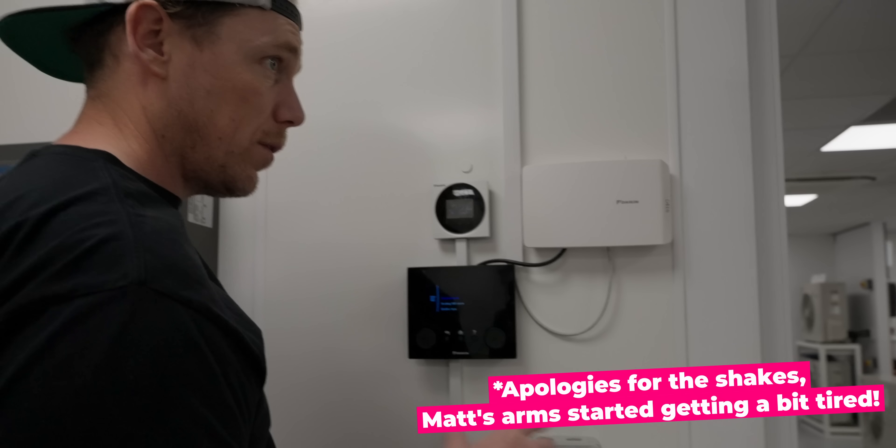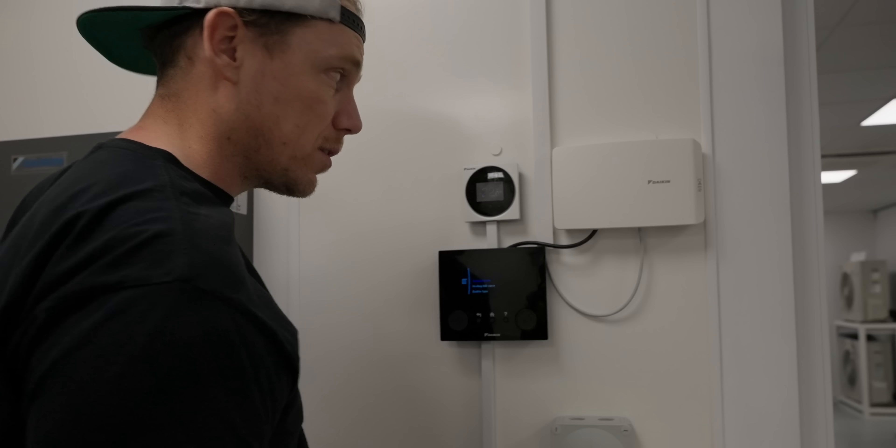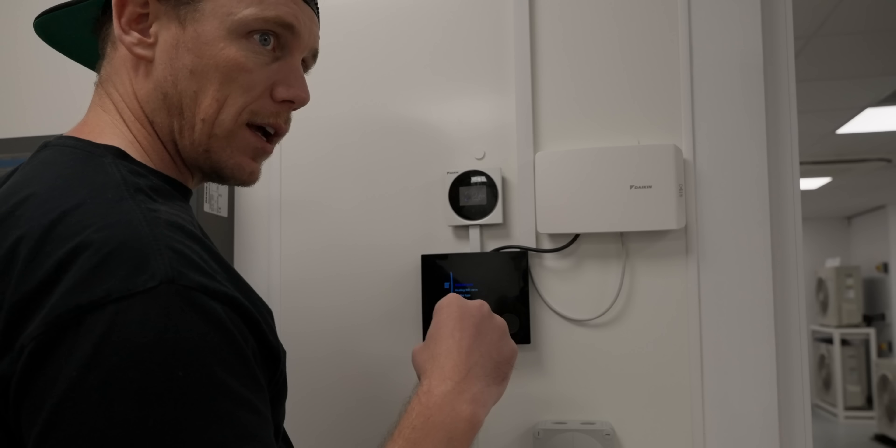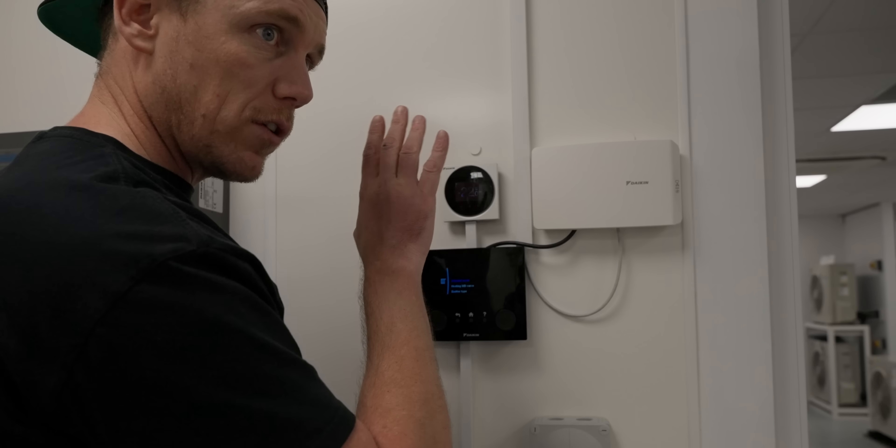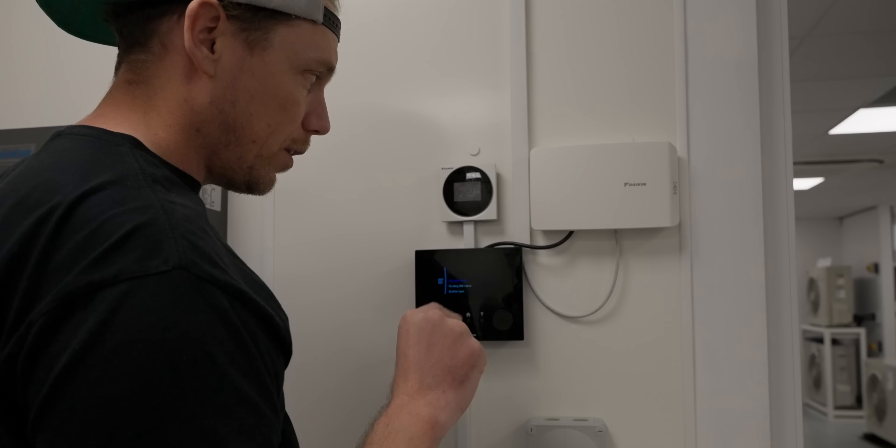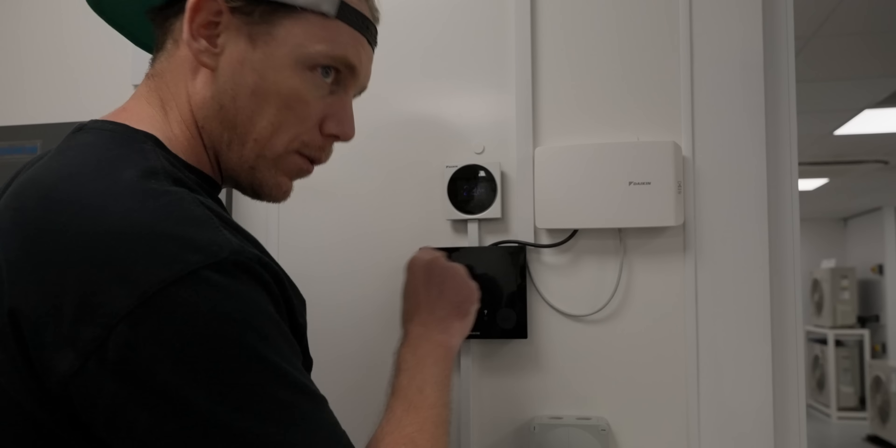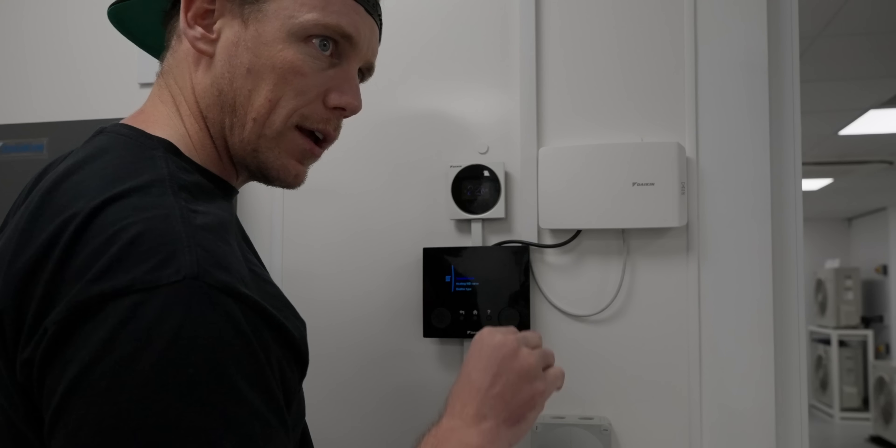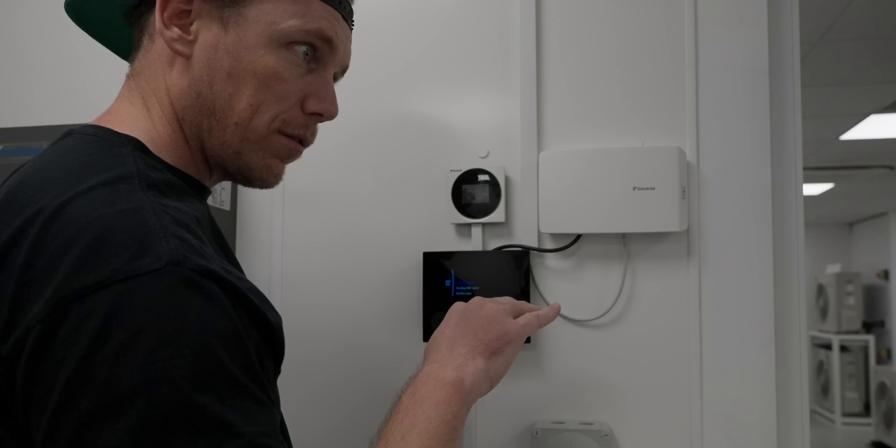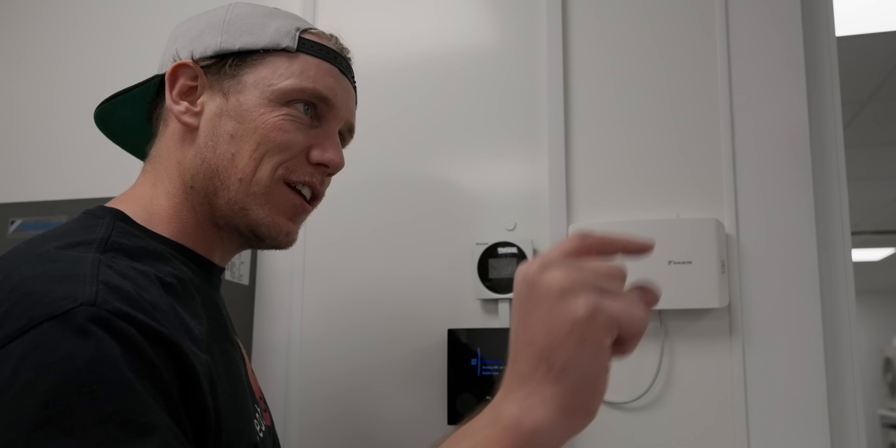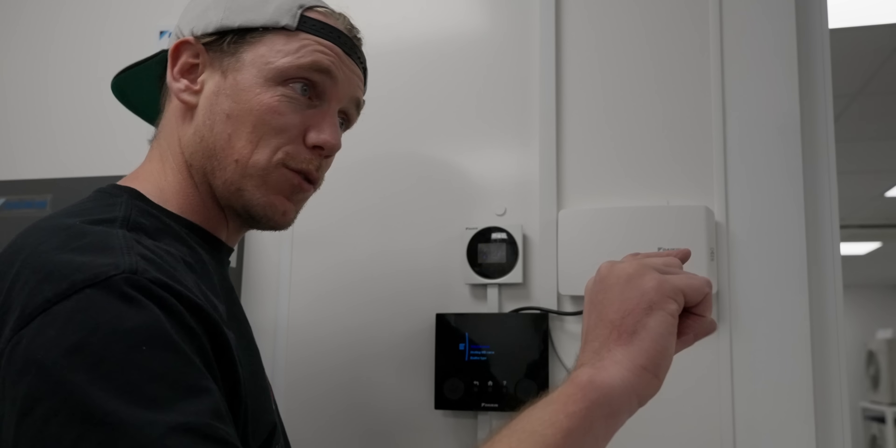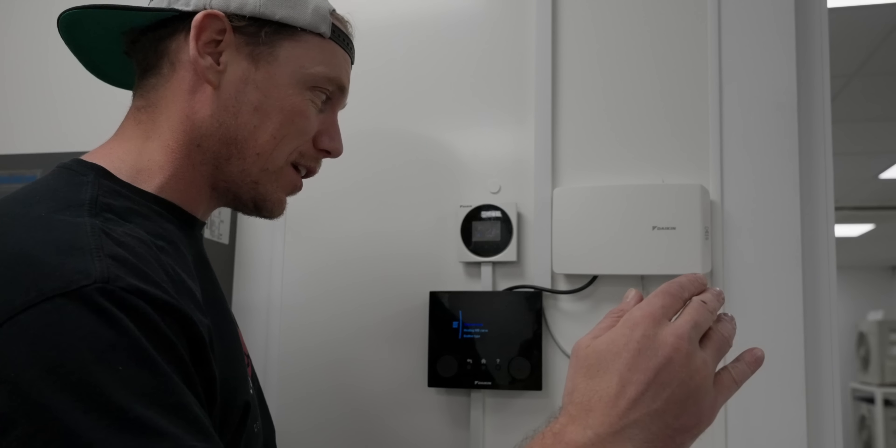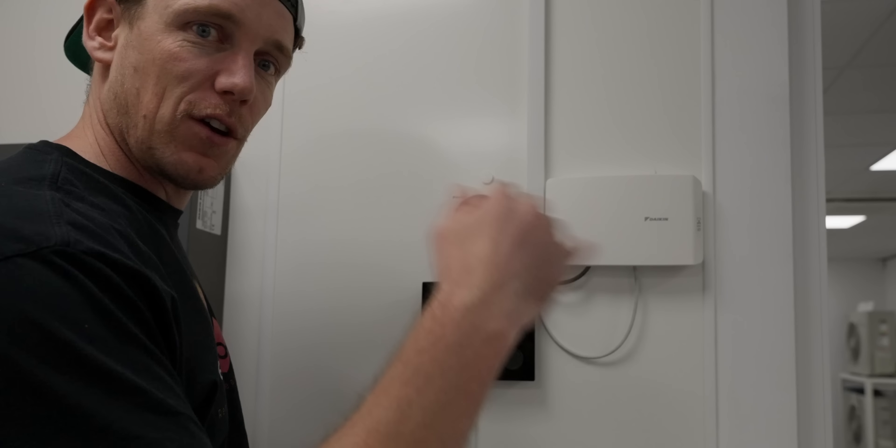The way we would advise to set up a system would be for the first six months, turn all of your individual room stats, even if it's on the floor, to 35 degrees room temperature. Then if you're too warm we go in, dial down your curve. We play around with the curve till the curve gets them to 20-21. Then we'll turn the room thermostats down to one or two degrees above the weather compensated temperature so they'll act as an overheat limit.